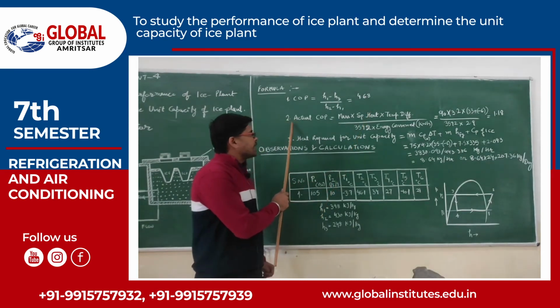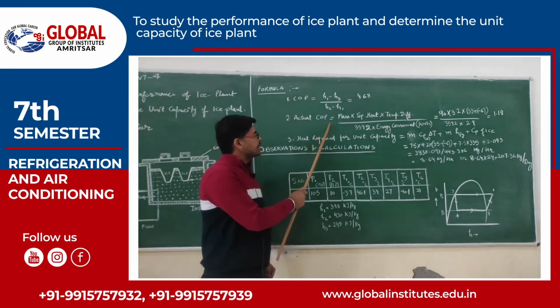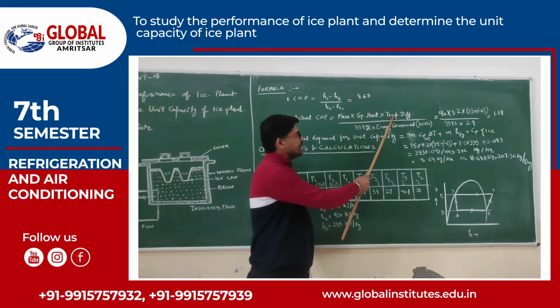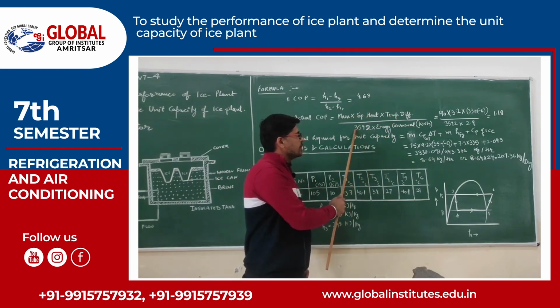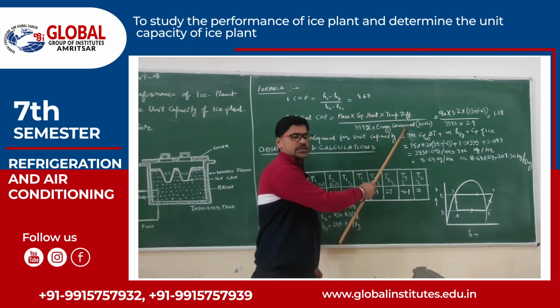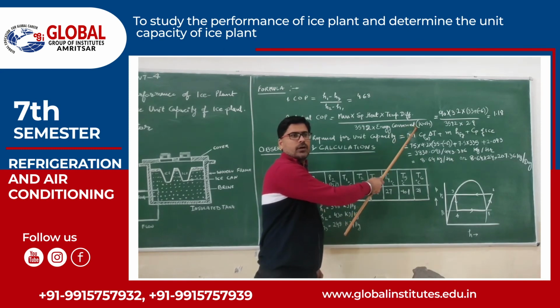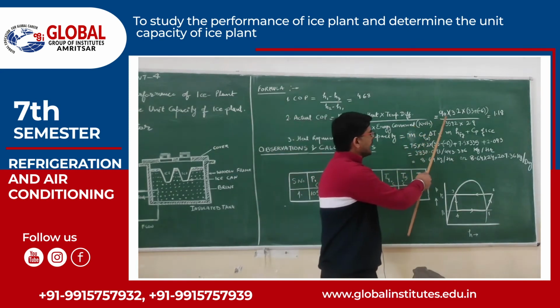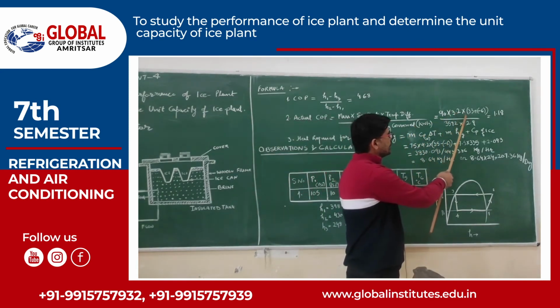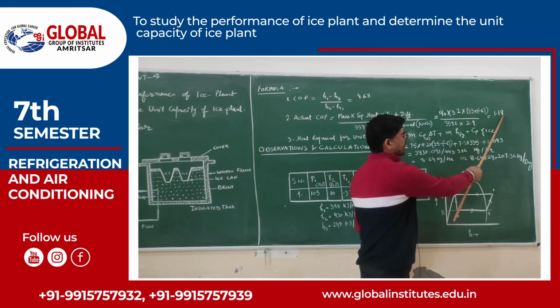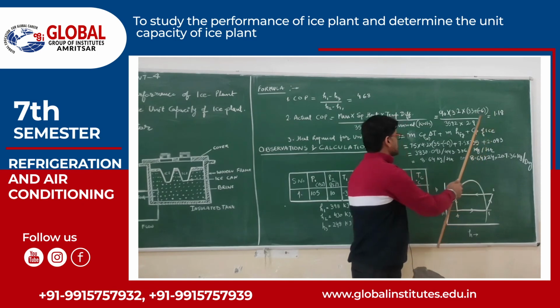Second part is the actual COP, that is equal to m Cp delta T upon this value into energy consumed by the compressor in kilowatt hour, that is equal to 90 into 3.2 into temperature difference upon this, which is equal to 1.18. This is the actual COP of the system.